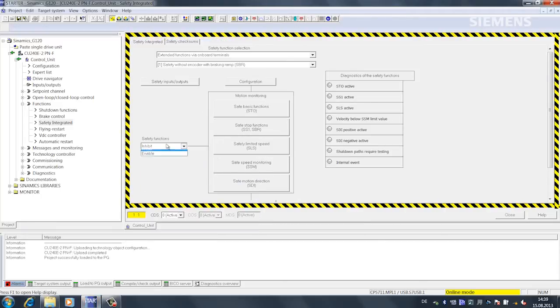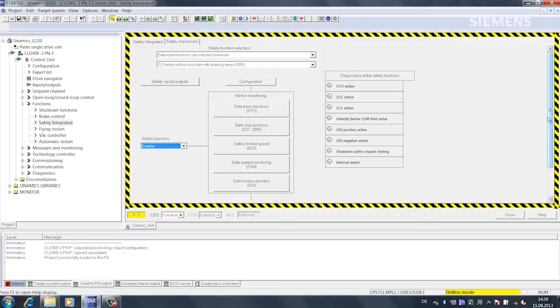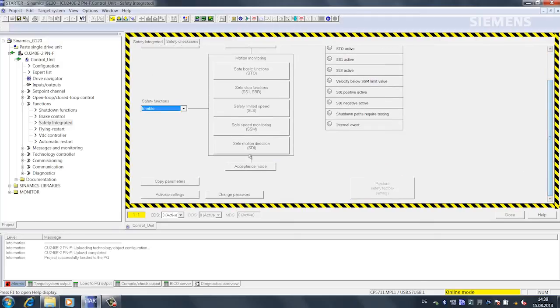Now I'll enable the safety functions and copy the parameters. Since we are parameterizing safety settings, all the parameters in a drive are redundant. The copy process writes this data to the second parameter.